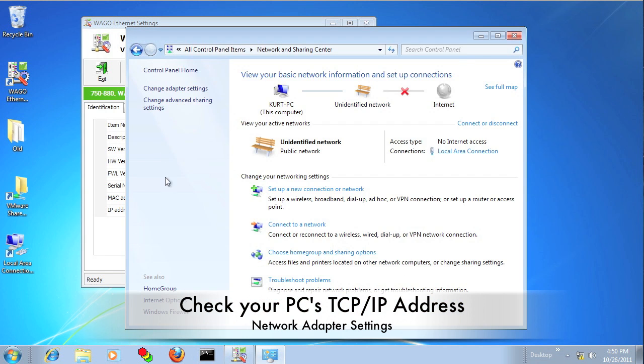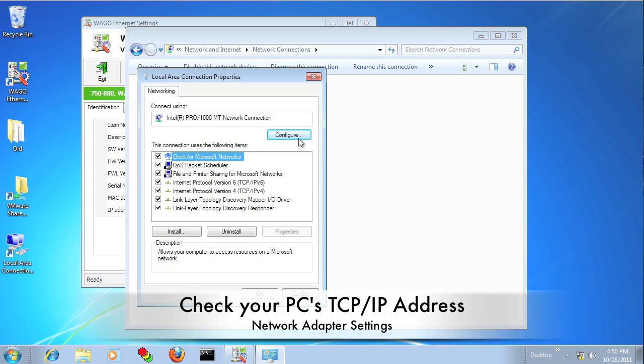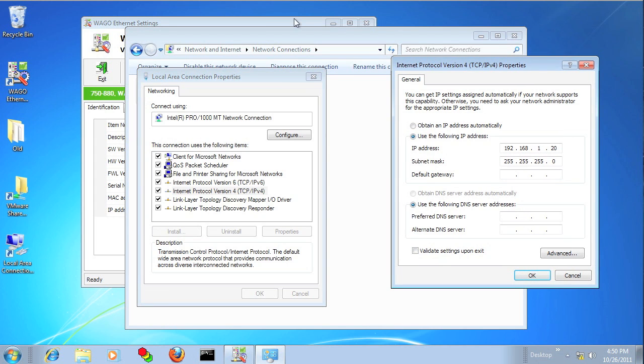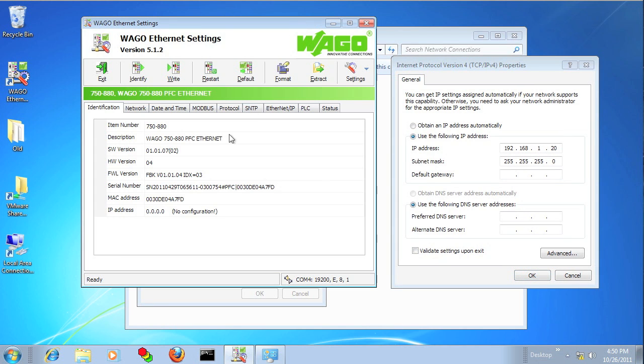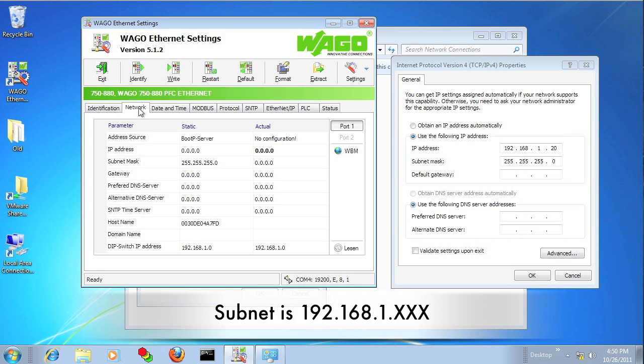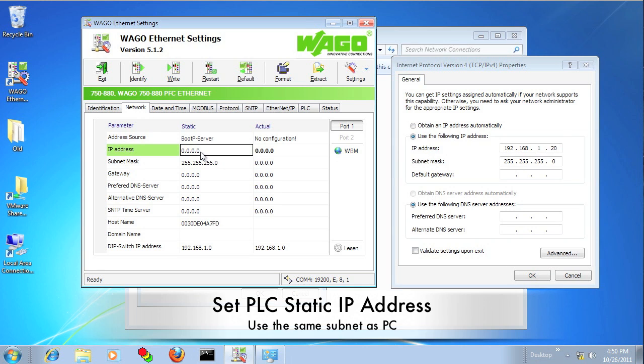Now we want to make sure that we put the PLC on the same subnet as our computer. So going into the network settings, you can identify the IP address that your PC has. And then we just want to choose an IP address for the PLC on that same subnet. In this case, it's 192.168.1, and we're just going to make it 3 for the PLC.